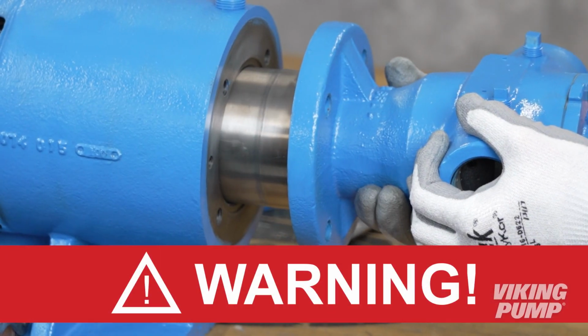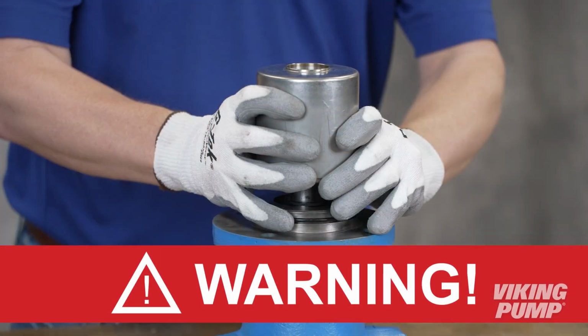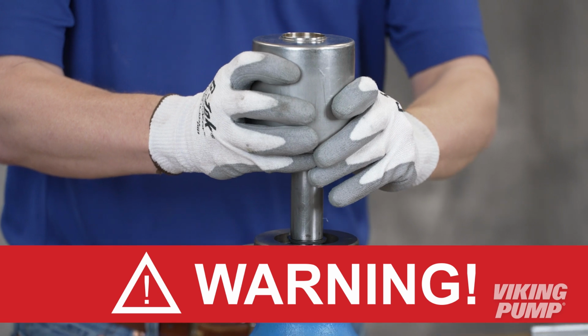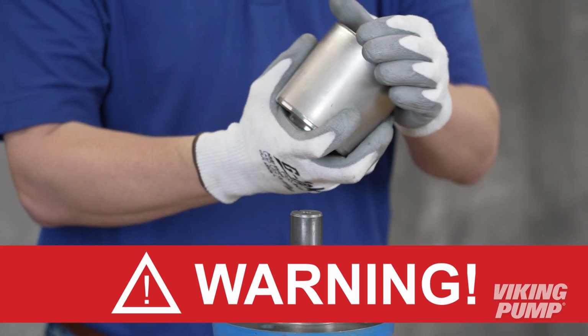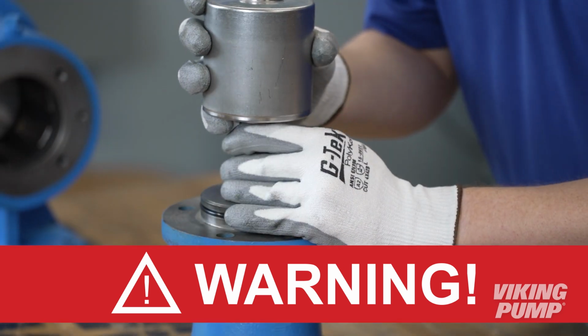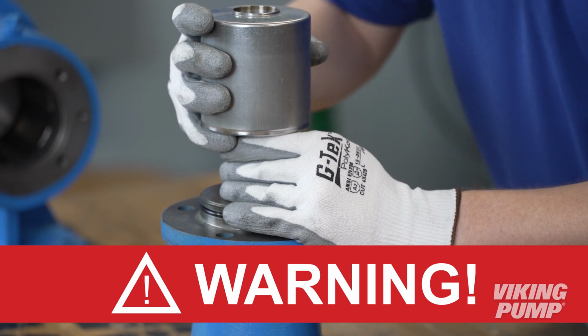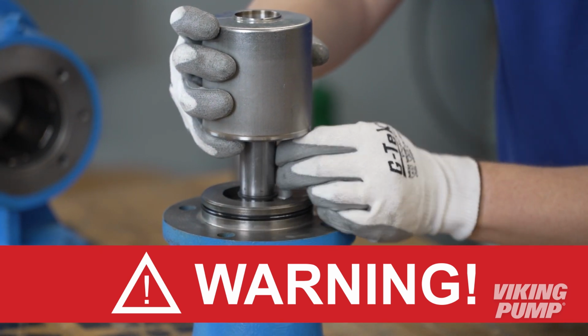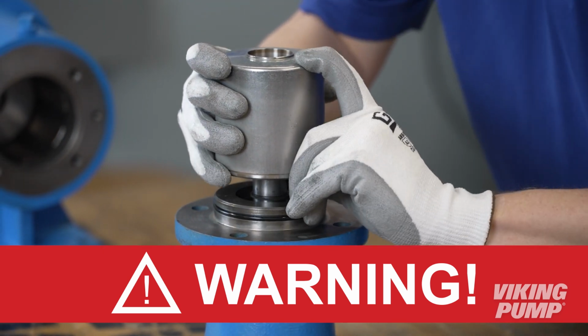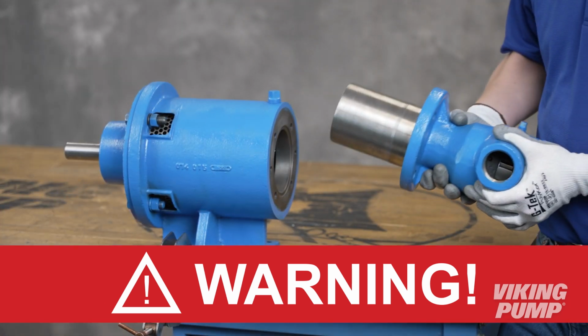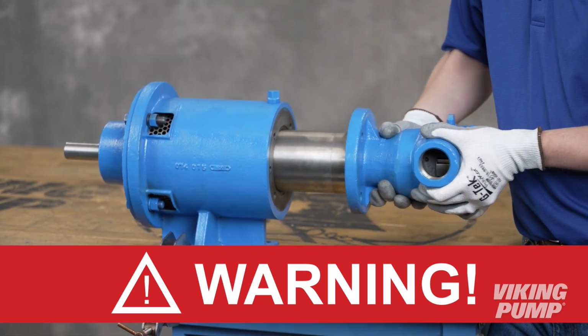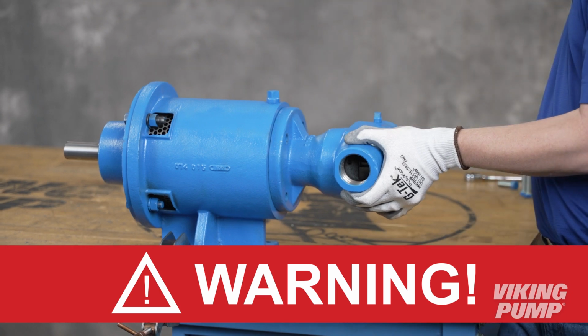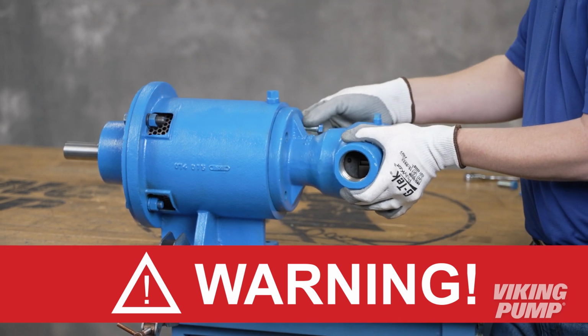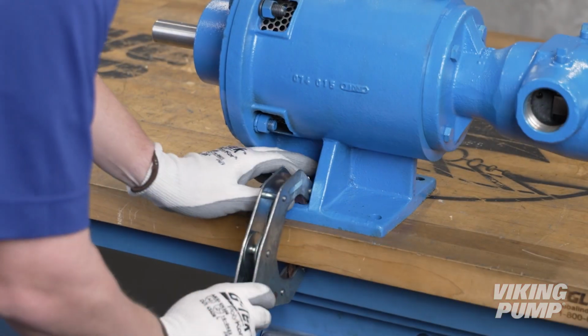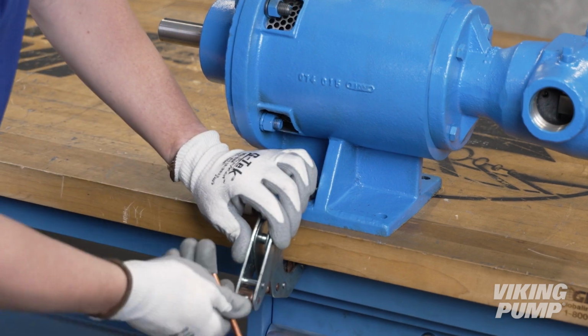Warning: rare earth magnets, like those used in the magnetic drive coupling, have extremely strong magnetic fields and are capable of changing the performance of or damaging items such as pacemakers, metal implants, watches, computers, cellular or mobile devices, and credit cards. Keep the pump and work area as clean as possible when working with rare earth magnets. It's important to work on a non-magnetic surface and to keep metal tools away from the magnets. Next, ensure the pump is secured to the workbench.